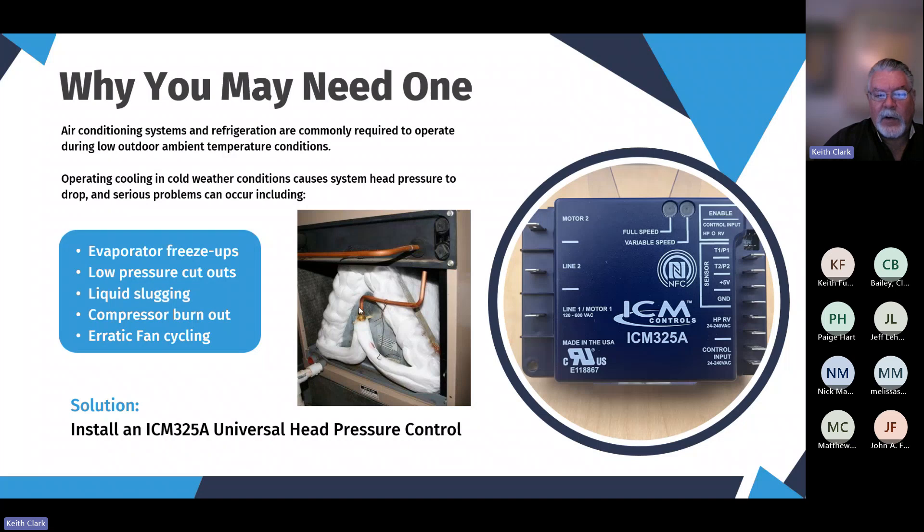We've got an illustration of that here. This is a common indoor A-coil that sits inside your furnace — usually your air handler — and that's where the cold air is developed with this cold evaporator coil. Operating cooling in cold weather can cause head pressure to drop, and then these indoor coils can freeze up. Obviously you can't get airflow across a coil that is frozen up, and it can cause other problems as well.